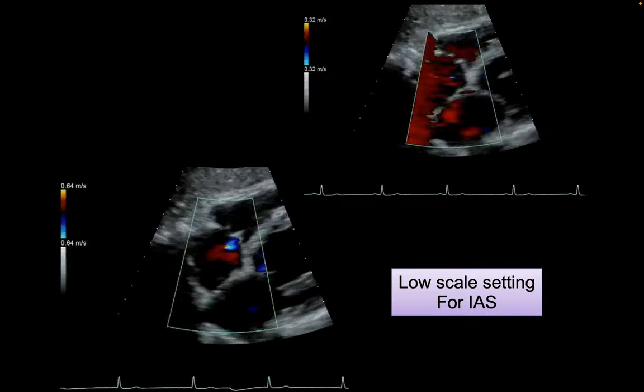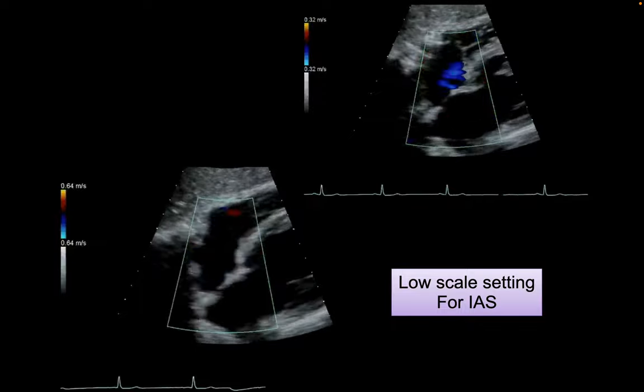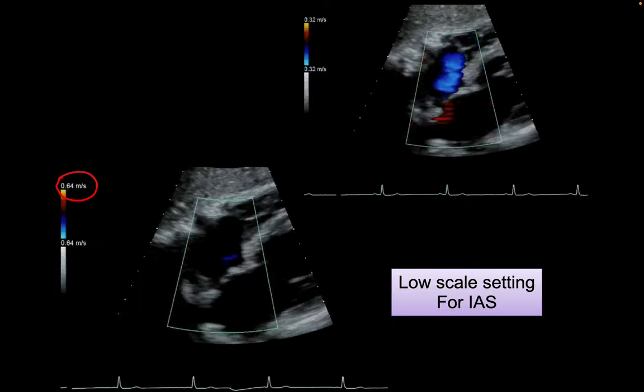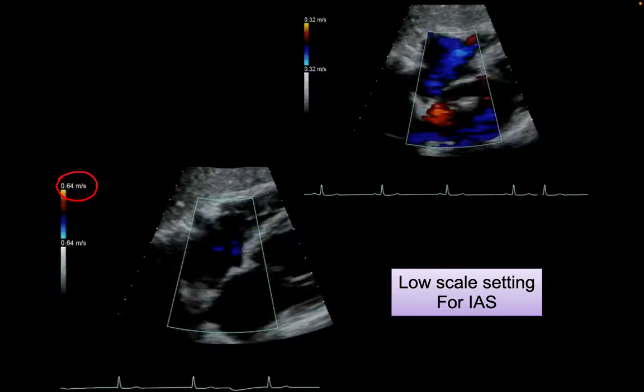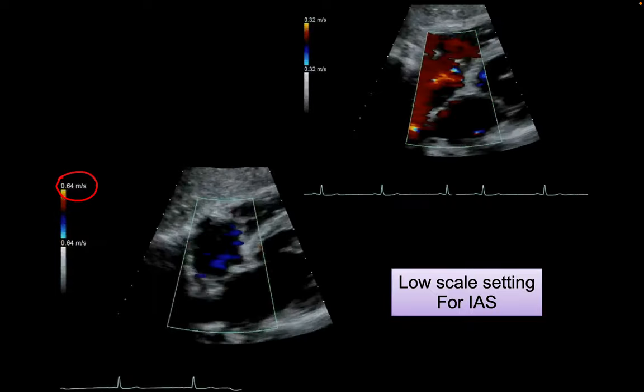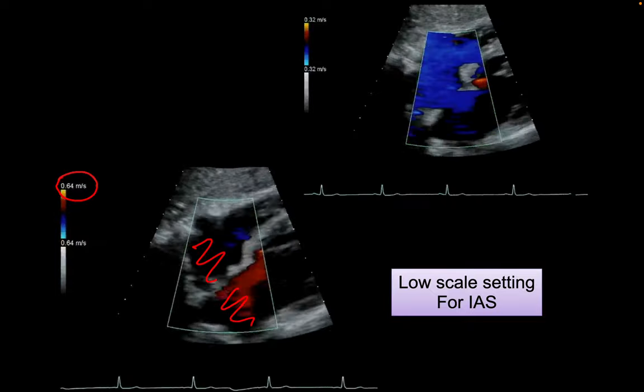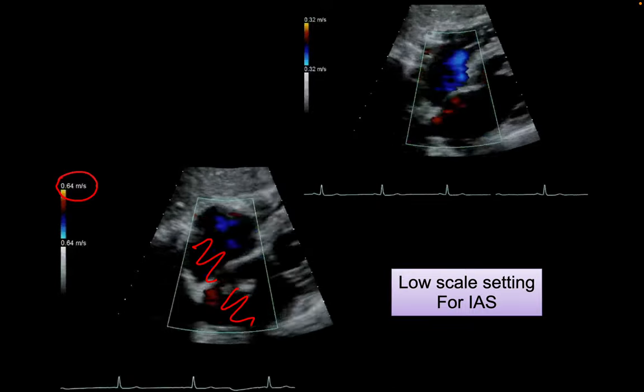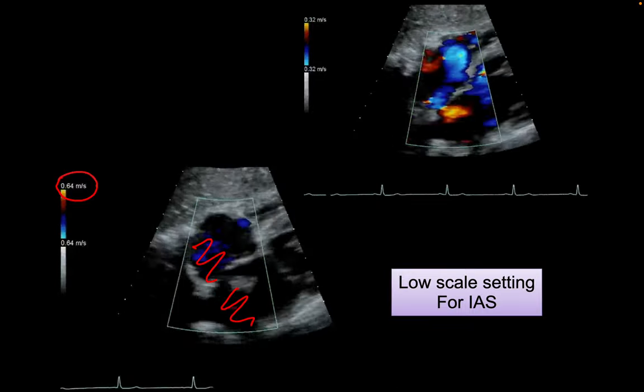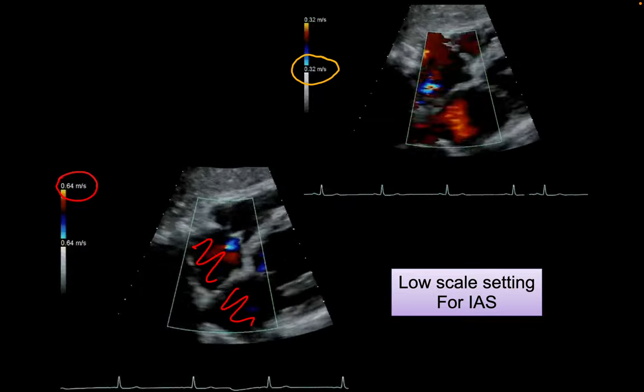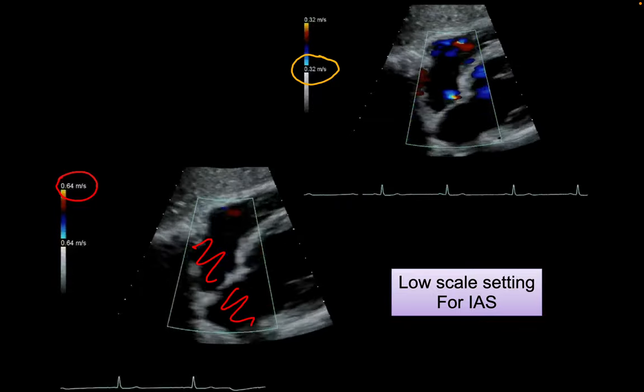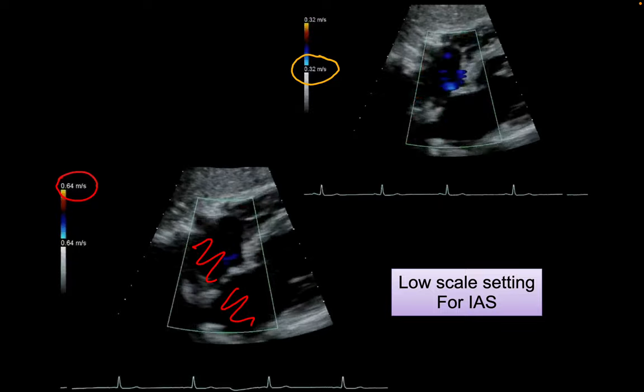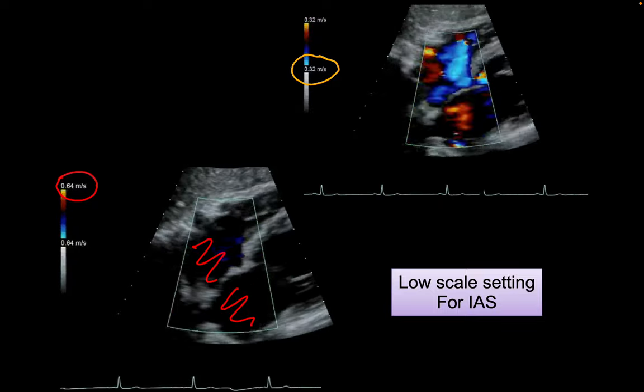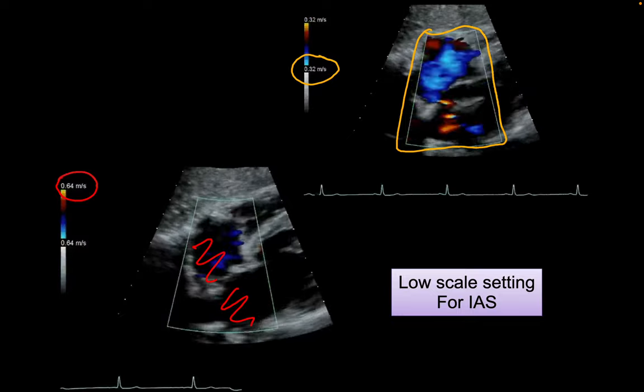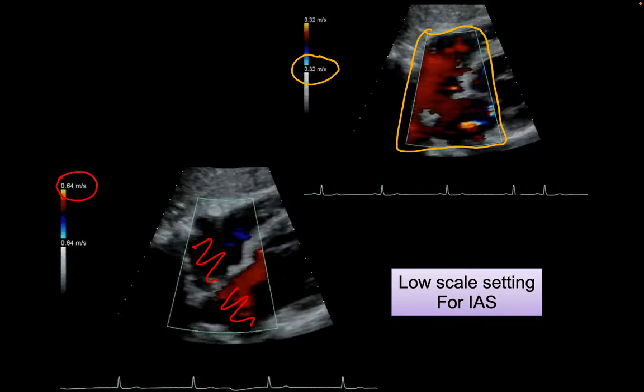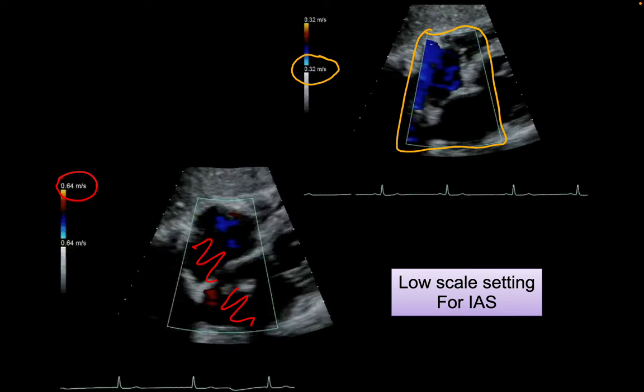Compare the two images. When you're setting 0.6 meters per sec, you can't see much. There's no flow at all. It looks like there's no flow in these areas. But when you set your velocity scale into that 30 centimeters per sec range, suddenly you will find nice flow in both atria. And this is how you assess the interatrial septum.